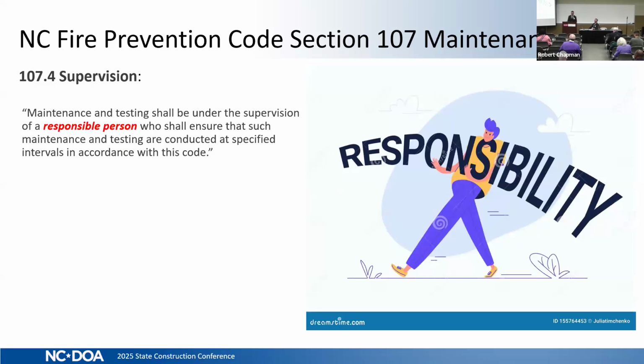All right. So supervision under the North Carolina Fire Prevention Code: maintenance and testing shall be under the supervision of a responsible person. This is the person that has to take in all of these codes, digest them, apply them to their facilities, and make sure the maintenance is done and the record keeping is done. I have a whole higher level of respect for our maintenance folks after going through this, especially as you see the other code books piling on with the references to maintenance. So they have to be aware of this.